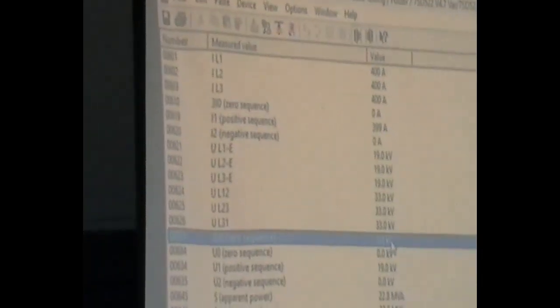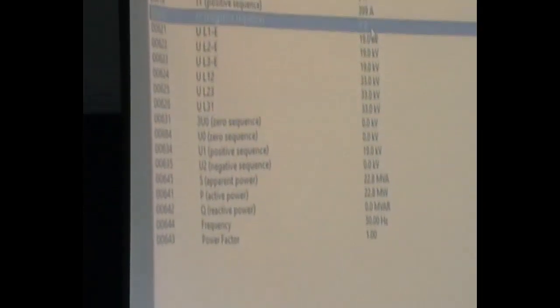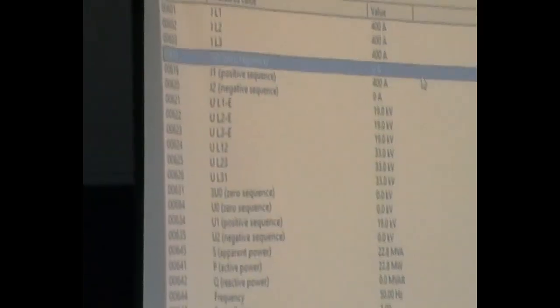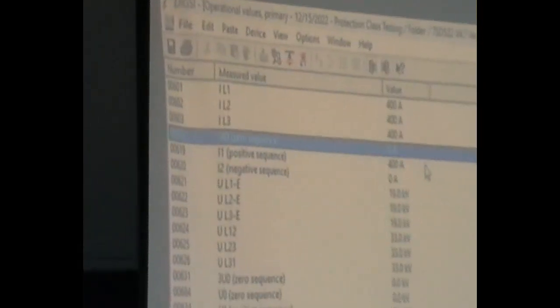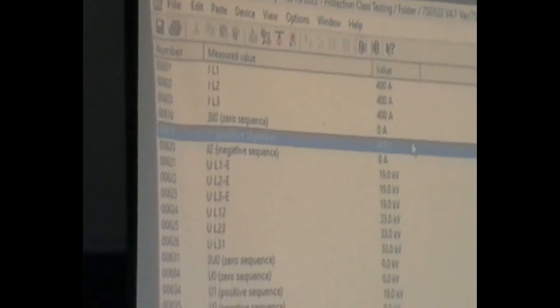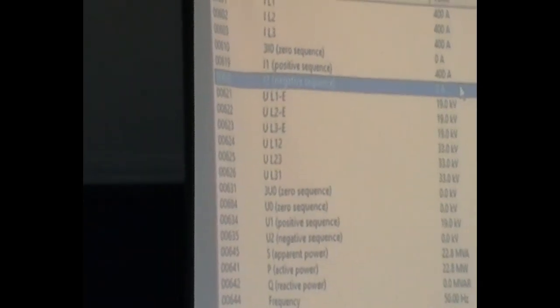Zero sequence in the current should be zero. Yes, zero sequence is 0. Positive sequence is 400 ampere because I'm only injecting positive sequence, balanced current, and negative sequence is again 0. The same goes for the voltage.